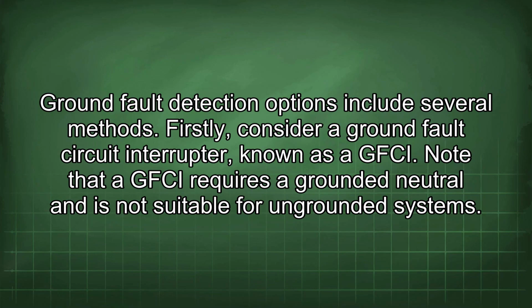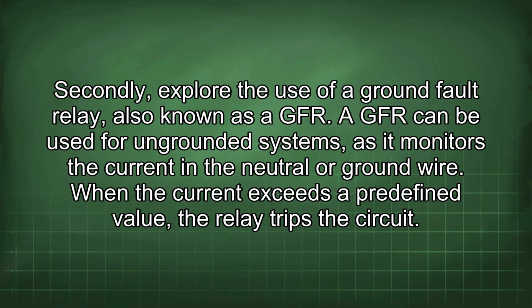Ground fault detection options include several methods. Firstly, consider a ground fault circuit interrupter, known as a GFCI. Note that a GFCI requires a grounded neutral and is not suitable for ungrounded systems. Secondly, explore the use of a ground fault relay, also known as a GFR. A GFR can be used for ungrounded systems, as it monitors the current in the neutral or ground wire. When the current exceeds a predefined value, the relay trips the circuit.